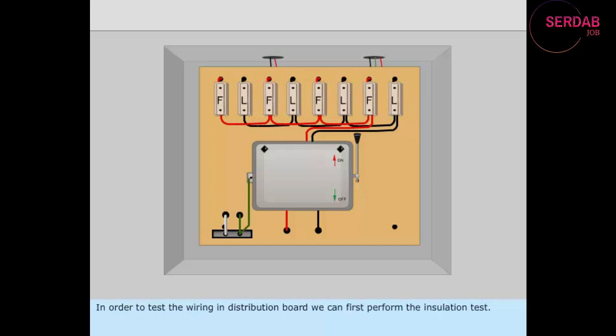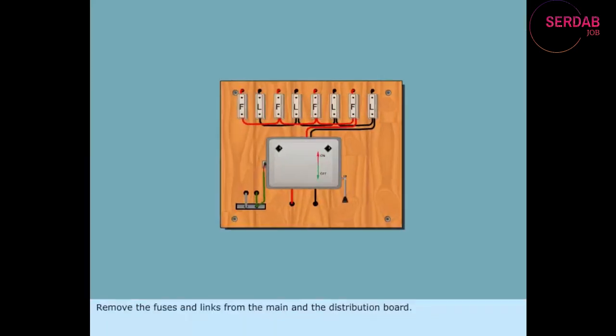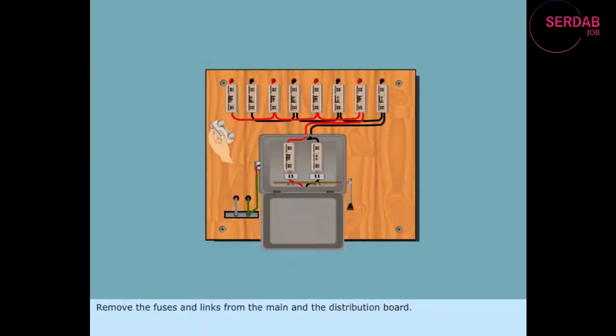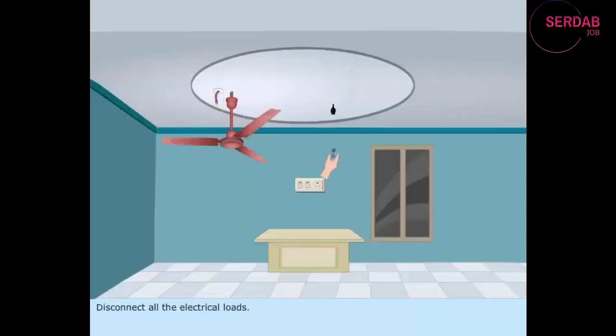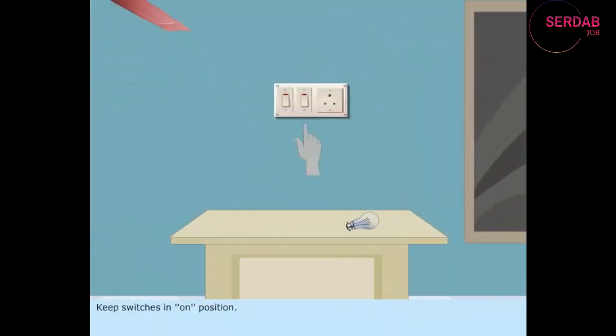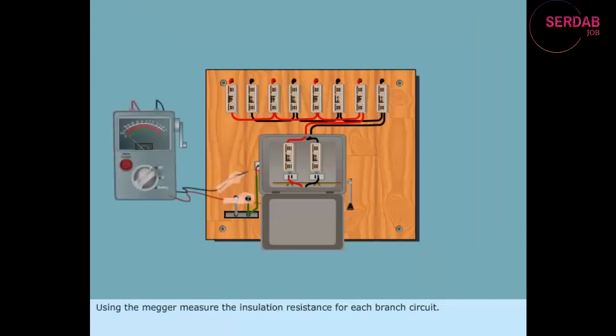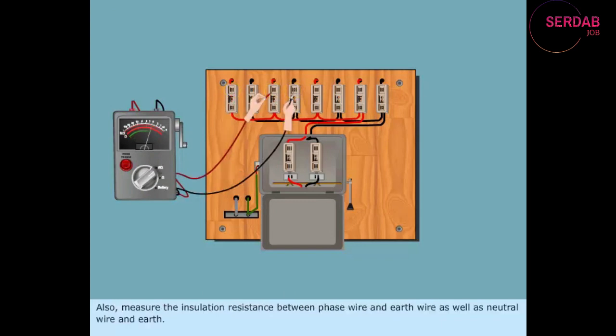In order to test the wiring in distribution board, we can first perform the insulation test. Remove the fuses and links from the main and the distribution board. Disconnect all the electrical loads. Keep switches in on position. Using the megger, measure the insulation resistance for each branch circuit. Also, measure the insulation resistance between phase wire and earth wire, as well as neutral wire and earth.